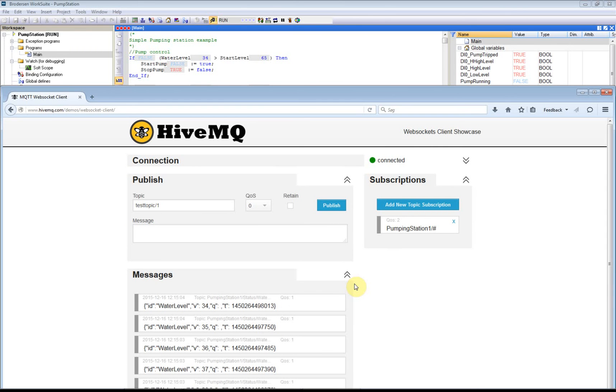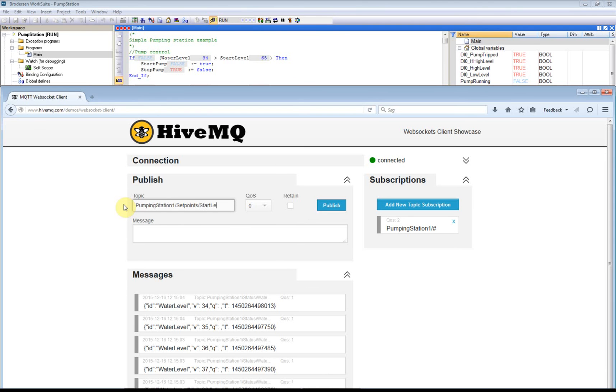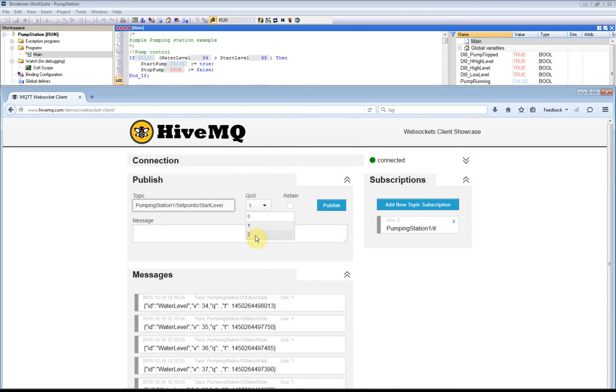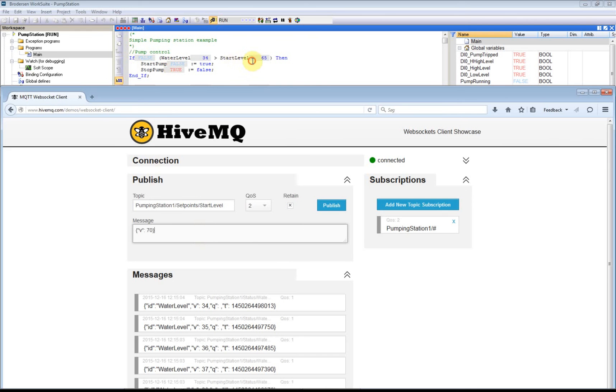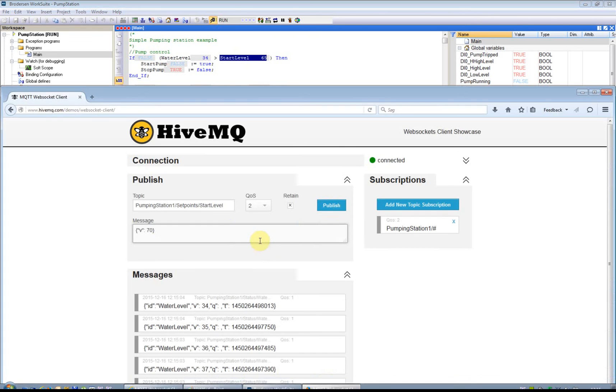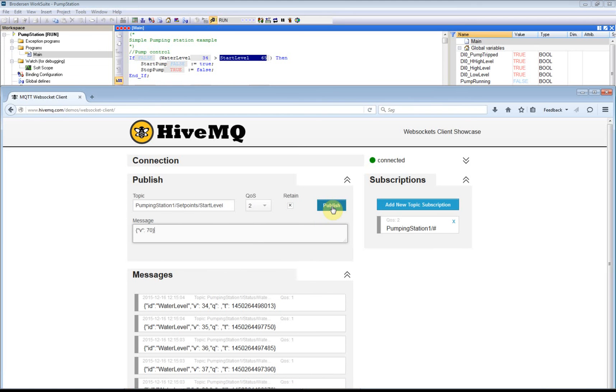Now I will try and change the Set Point for our starting level. My topic is PumpingStation1/Setpoints/StartLevel. We'll have it as quality of service 2. Then we'll be looking at the V field, and it should be 50 to 70. Currently you can see here our start level is 65. Now I'll publish this to our MQTT client.